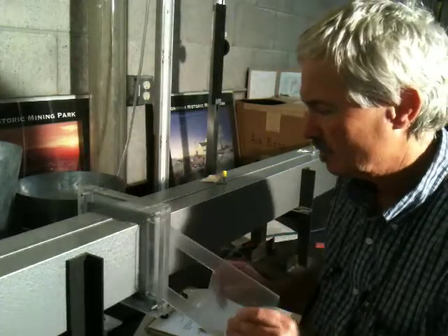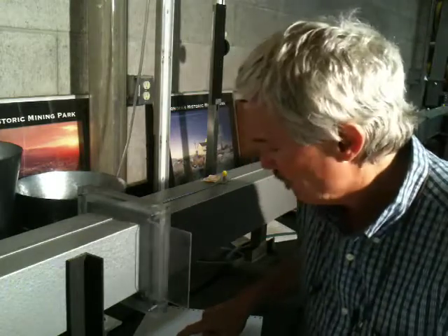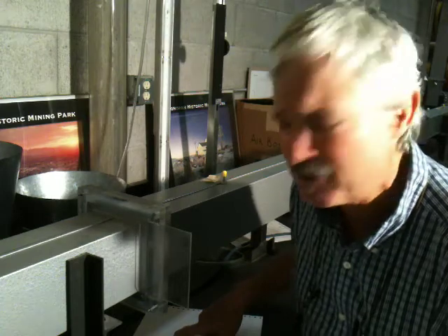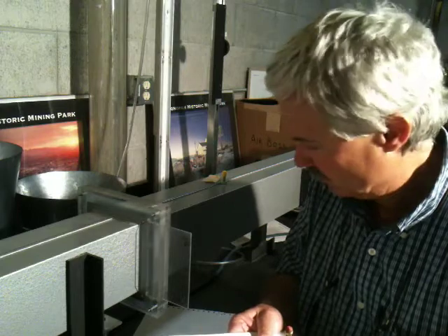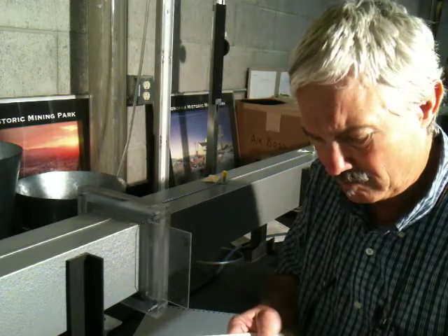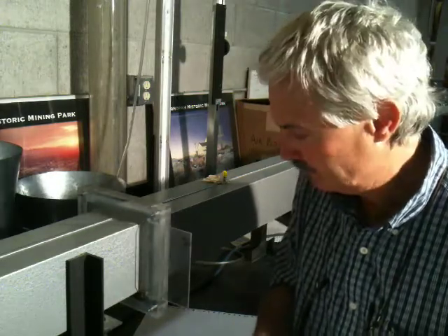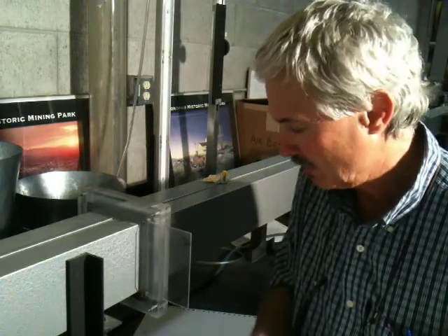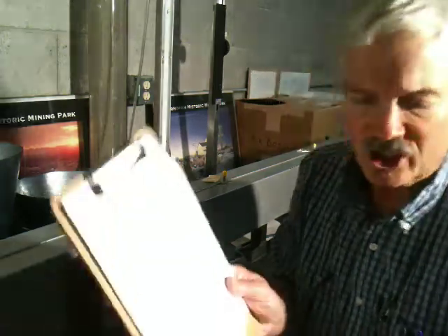So here's the 3 1/4 inch regulator. For the 3 1/4 inch regulator, the centerline velocity pressure up there at the pitot tube traverse station was 0.535 inches of water gauge. And delta static pressure is 1.938 inches of water gauge, okay? So there's the data sheet.